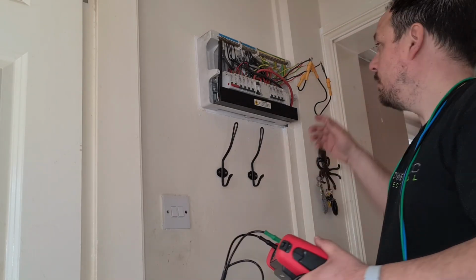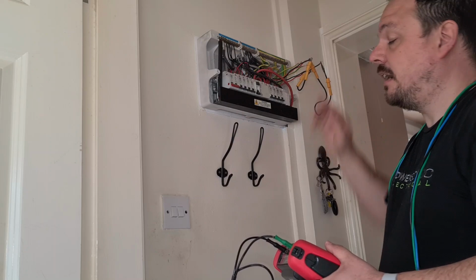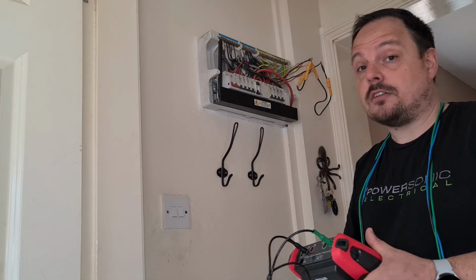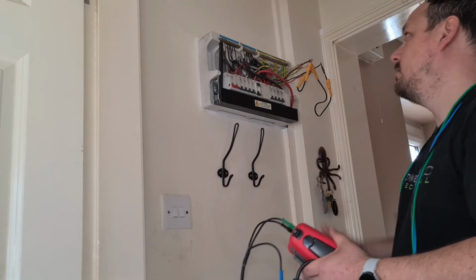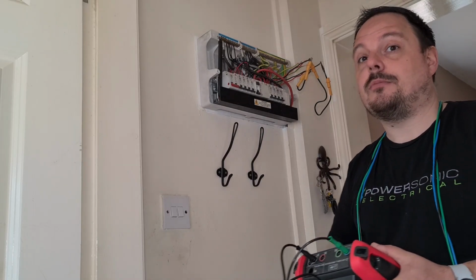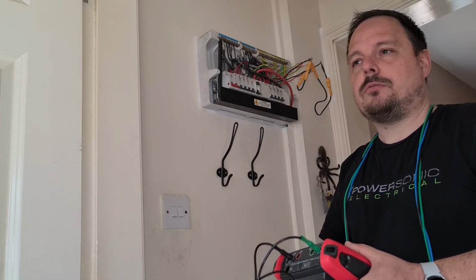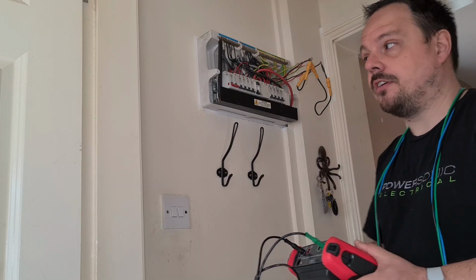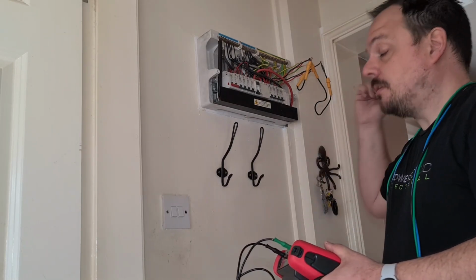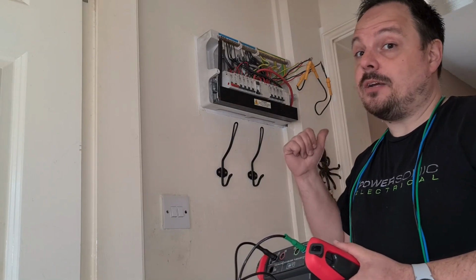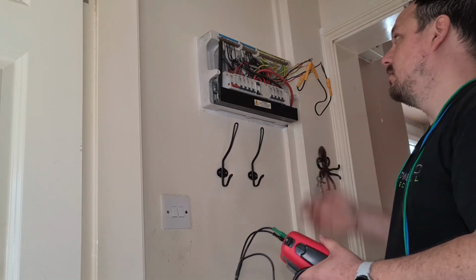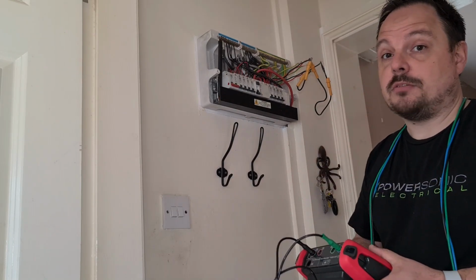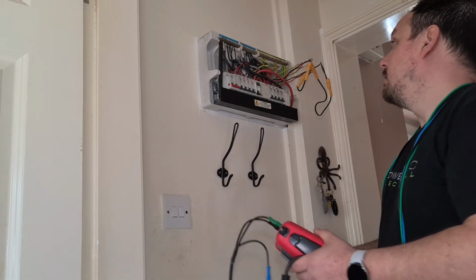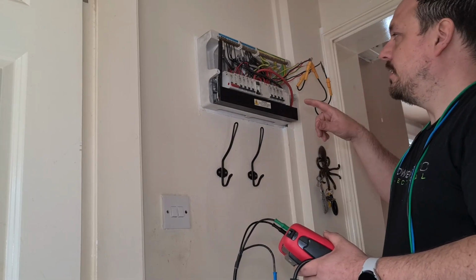Okay, so I've just repeated that process now for the R1 and Rn. It's not a test you need to record on the test sheets anywhere, but it is sometimes worth doing, and especially in this case when we've had water everywhere, it's a good way of verifying any of the terminations through the socket fronts, for example. This is a part of the building which supposedly hasn't seen any water ingress to anything, so it's well worth doing those checks if the accessories might not be getting swapped. So we've done that, and now we can look at the insulation resistance.